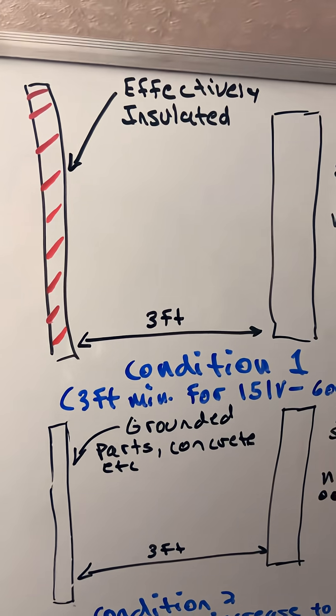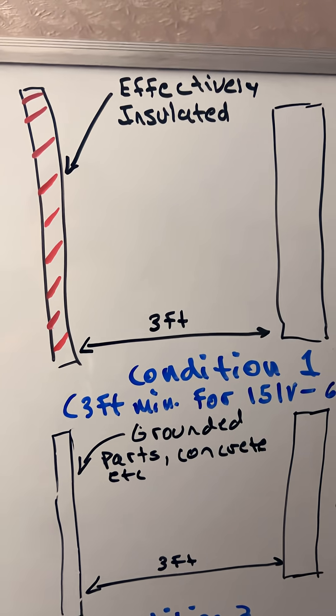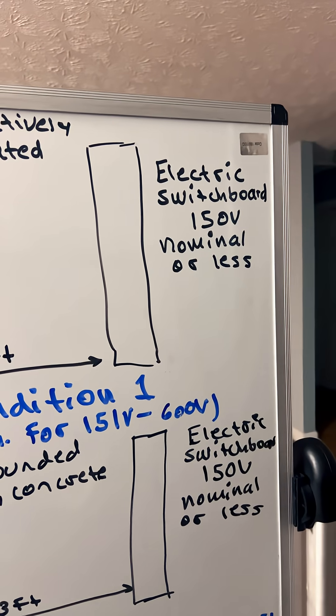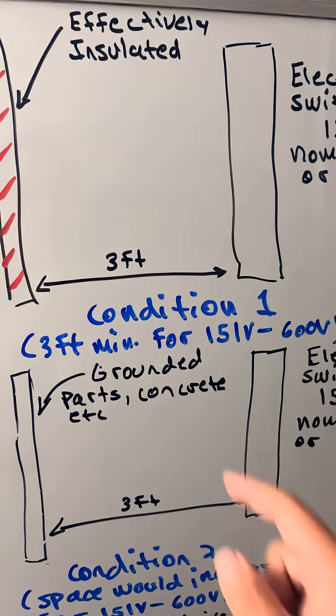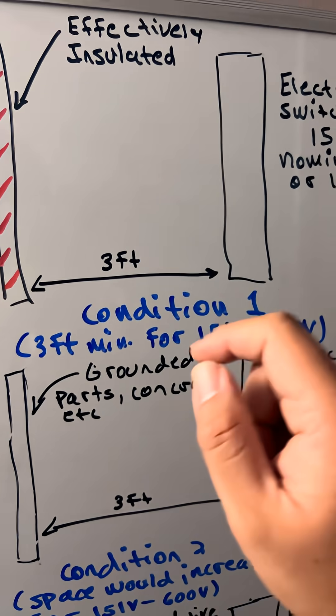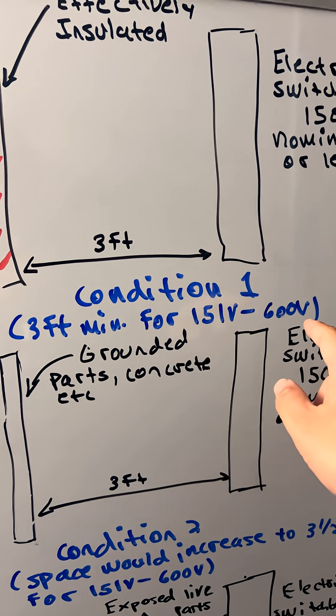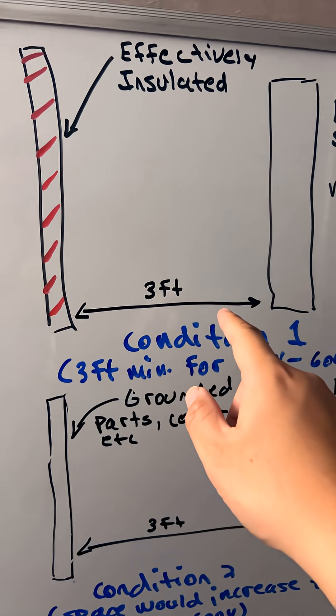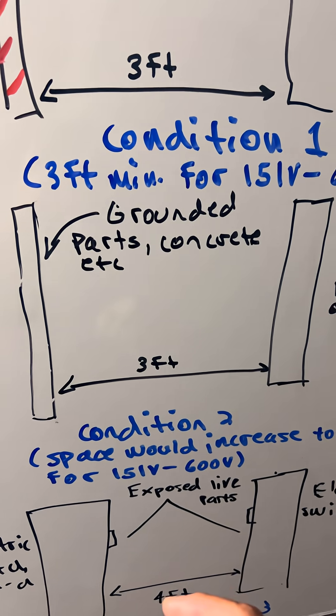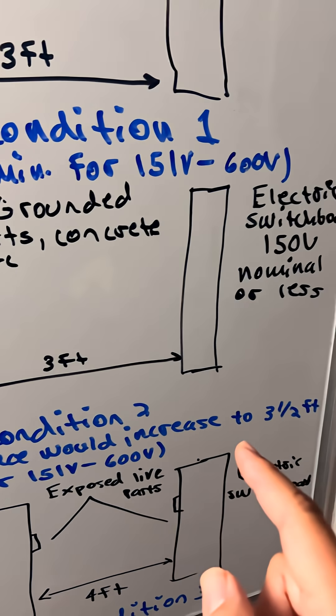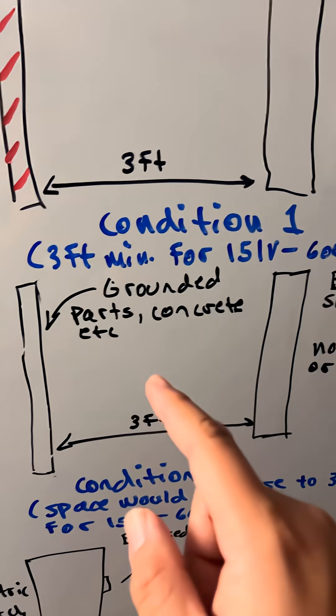As you can see here, on one side of the wall is the effectively insulated side, and on the other side we have the electric switchboard for 150 volts nominal or less. For condition 1, the minimum is 3 feet. For condition 2, the space increases to 3.5 feet for 151 volts to 600 volts.